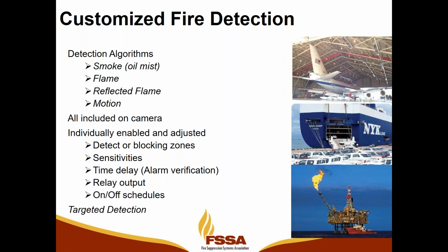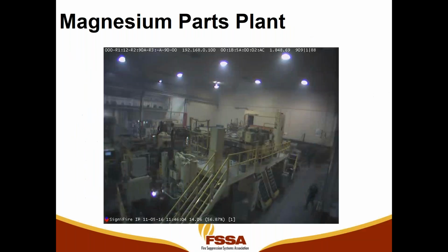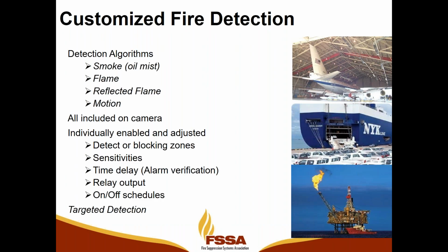The algorithms available are smoke, which is also used with oil mist, flame, reflected flame. Reflected flame with video analytics is the only means that I know of to detect reflected flame, unless it's a very large fire and you're using a radiant energy detector. Motion is also available. Within the software, there are settings to monitor the areas with the highest detection sensitivity and the lowest potential for false alarms.